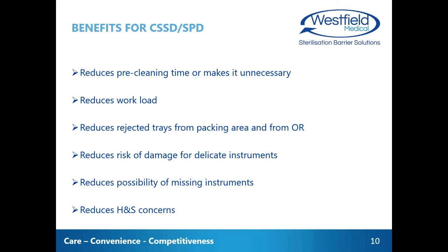But keeping the soil in soft state and therefore reducing the need for scrubbing and brushing. Of course, this also leads to a reduction in workload for the CSSD technicians. And the same thing, this reduces the risk for rejected trays, either from the packing area, which is probably the most common, or then even sometimes from the OR. As no brushing and scrubbing is required, the risk for damages for delicate instruments is reduced as well.